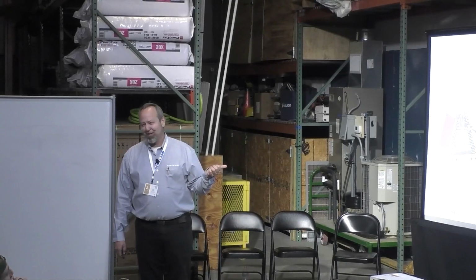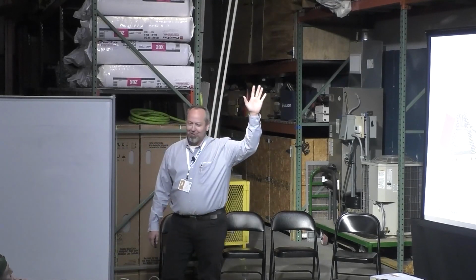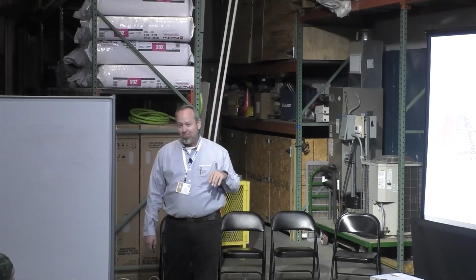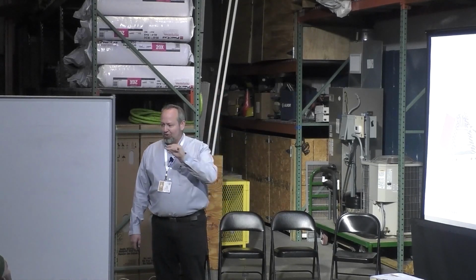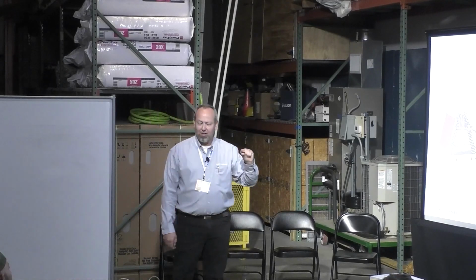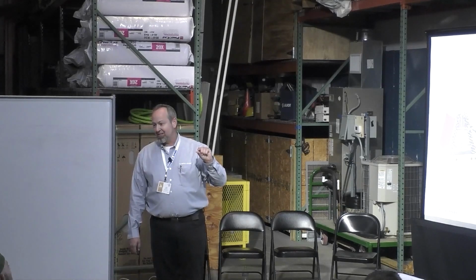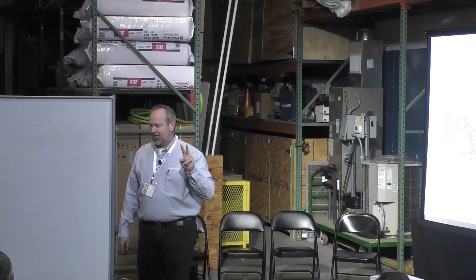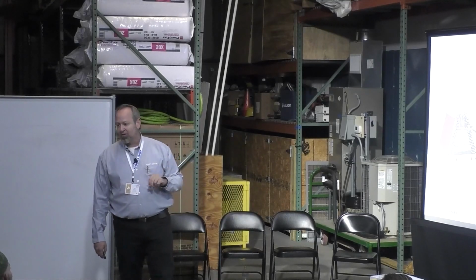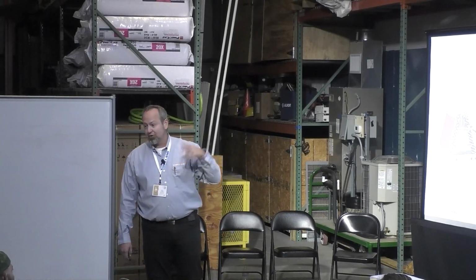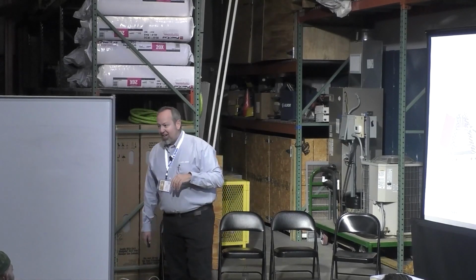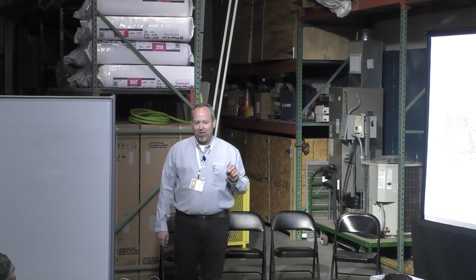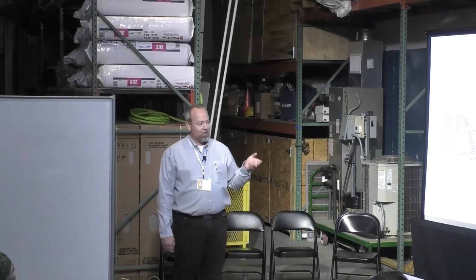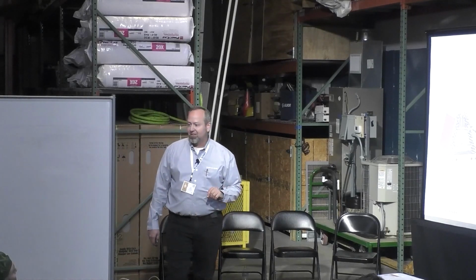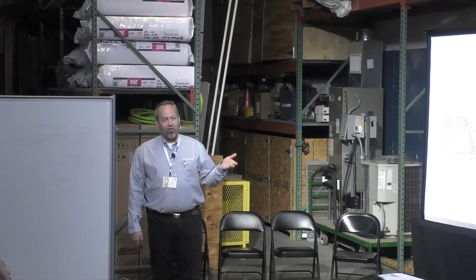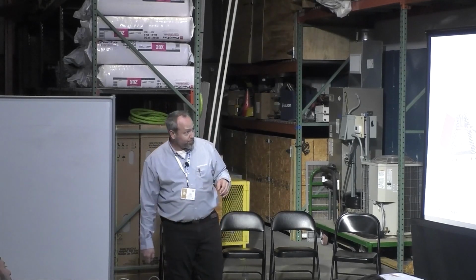Another story, microchannel. Everybody familiar with microchannel? Some people use it. It's still out there, I think, some today. Microchannel condensers are so flat. There's such a limited amount of storage in there, even in the AC only side of things, that 2 ounces of charge will make a difference. 2 ounces overcharged or undercharged in the system. 2 ounces undercharged, and it won't cool. 2 ounces overcharged, and you'll be blowing fuses. And so storage capacity in heat pumps, of being able to store that liquid, and the value of that accumulator is extremely valuable for that heat pump to run and to operate.